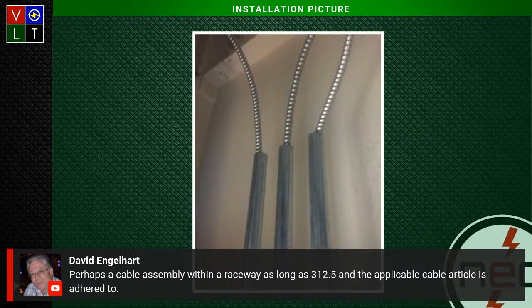As David Englehart mentions in the comments - let me pull that up real quick - you can have a cable assembly within a raceway, as long as 312.5 and the applicable cable article is adhered to. That's correct, David, you're absolutely right, and that's where I kind of went with this. There's really nothing that says you have to strip the jacket off to slide it inside a sleeve, EMT sleeve, or any kind of raceway sleeve.